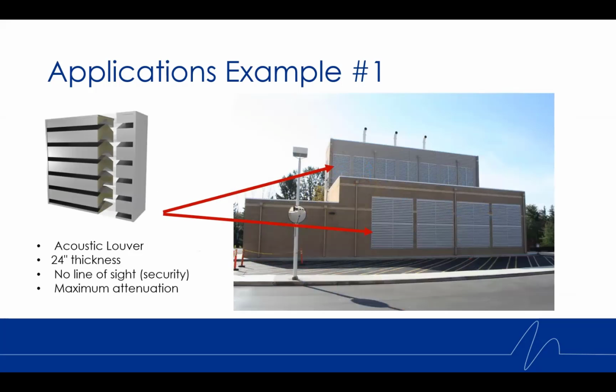So what we've done is, when this building was initially designed, these were typical architectural type louvers that were installed to allow airflow into and out of the building. We had replaced those with 24-inch thick acoustic louvers. Now in this case, you can see a bit of a profile of the blade that we used here. It's a chevron shape. That just allows for extra noise control and also allows for blocked line of sight. So someone who's walking by wouldn't be able to peek between the blades and see what's happening in that building. So it adds a little bit of extra security.